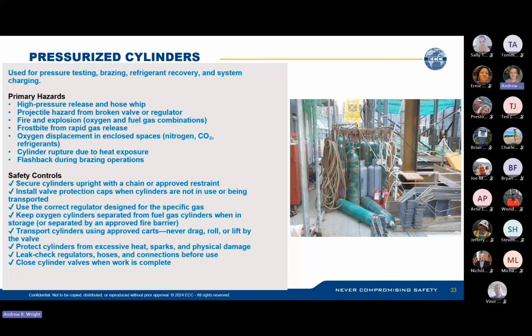If a pressurized cylinder falls and the valve stem breaks off, that cylinder basically turns into a missile. So you've got to make sure that it's secured at all times, one way or the other. Other hazards are frostbite from rapid gas release, oxygen displacement in enclosed spaces if they're using CO2 or nitrogen, cylinder rupture due to heat exposure, and then flashback during brazing.